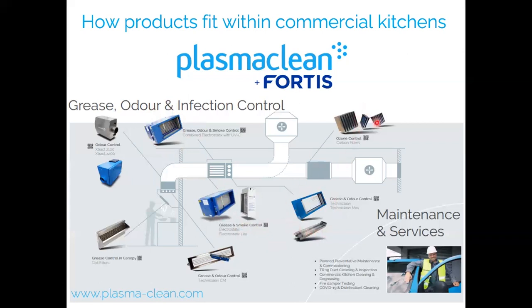Finally, as you can see here, the last two products: we've got a Techniclean unit, which is essentially a bolt-on to the ESP UV, and that's for grease and odour control only. And also we've got activated carbon filters. In situations where the discharge point is at high level, you don't need carbons, whereas at low level, to act as a residual ozone removal tool, we use carbon filters.